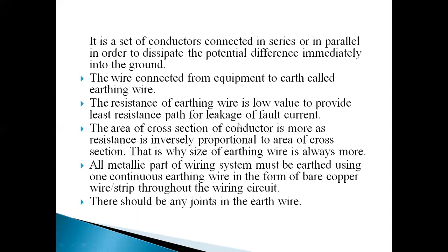So the area of cross-section of the conductor is more, as resistance is inversely proportional to the area of cross-section. We observe this A in the formula of resistance. R can be given as rho L by A. That means resistance is inversely proportional to area. So if the cross-sectional area is more, then the resistance of that particular wire will be less. So that's why we have to choose the conductor whose cross-sectional area is more. Okay, that is why the size of the earthing wire is always more.